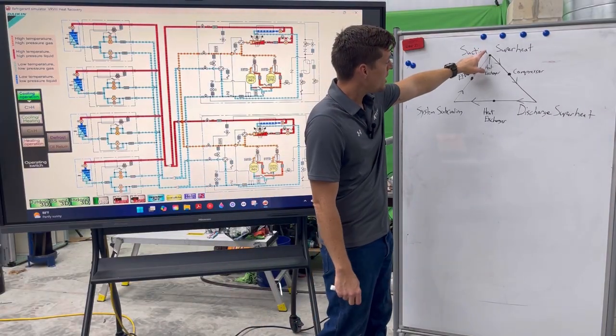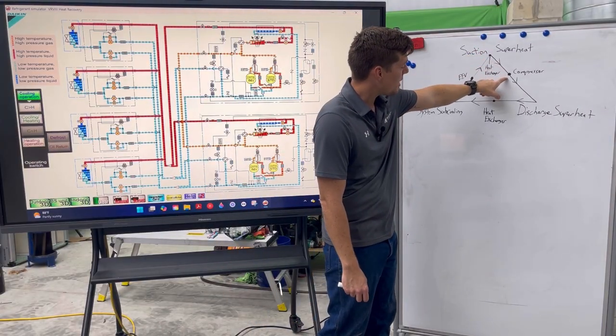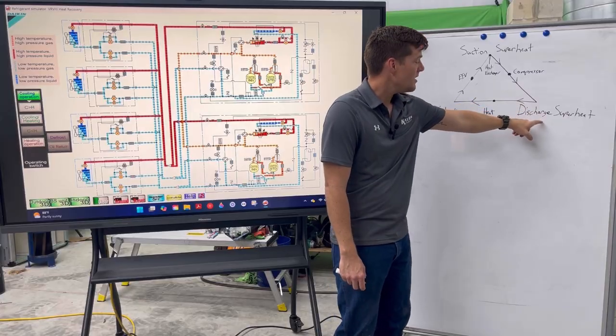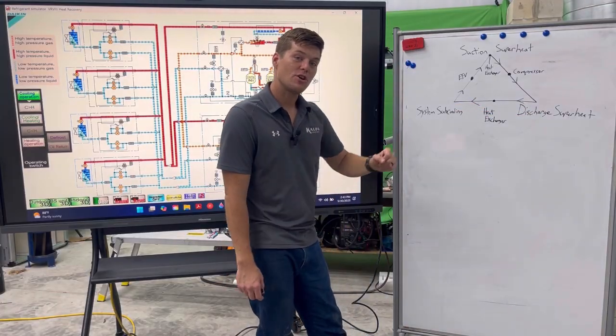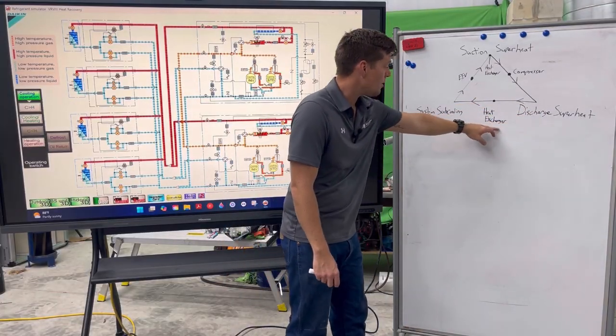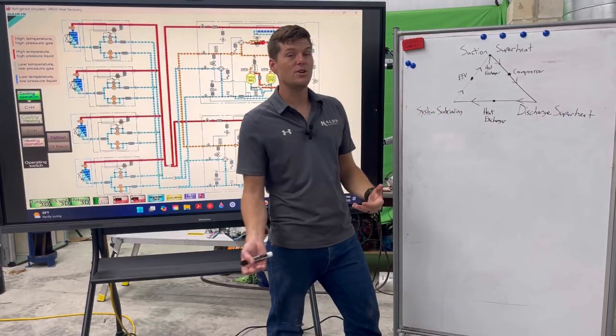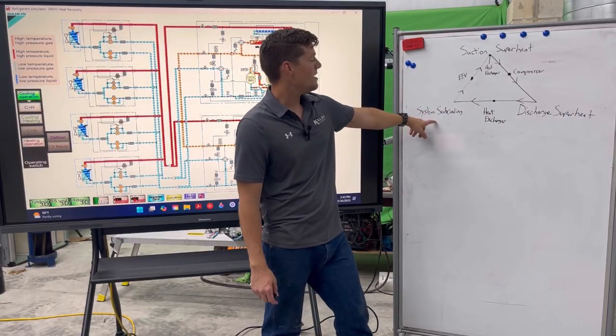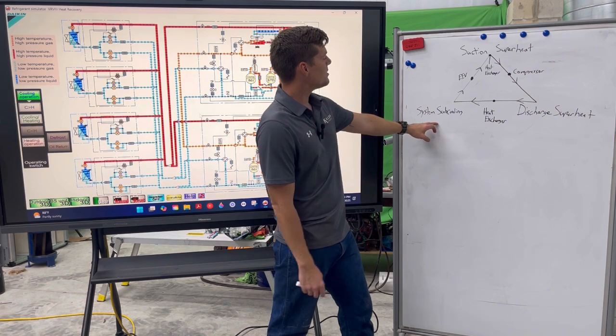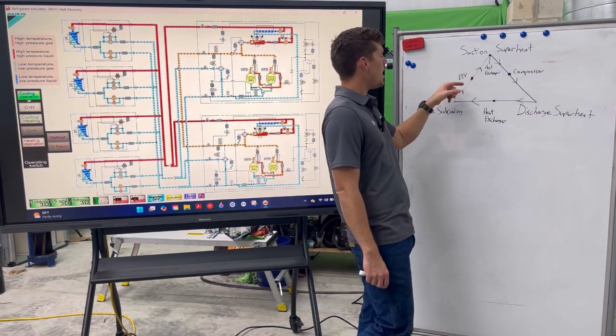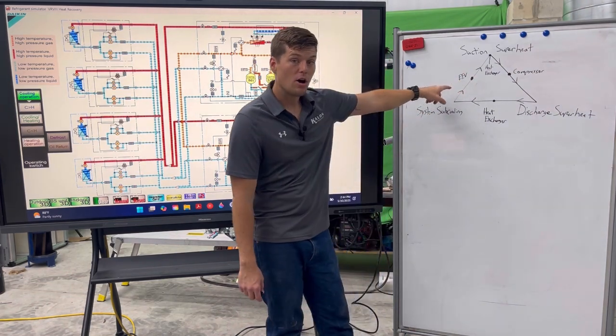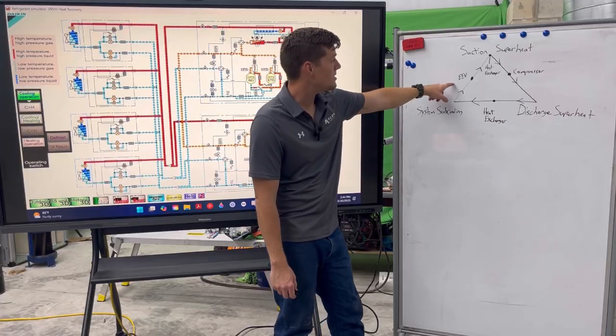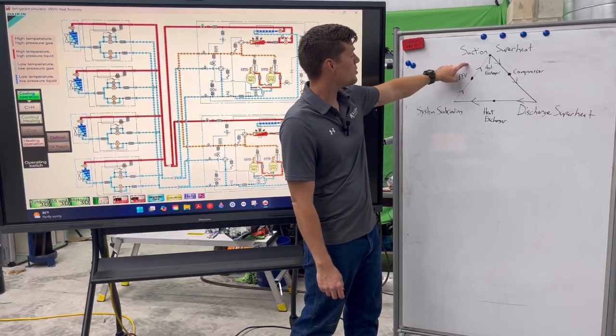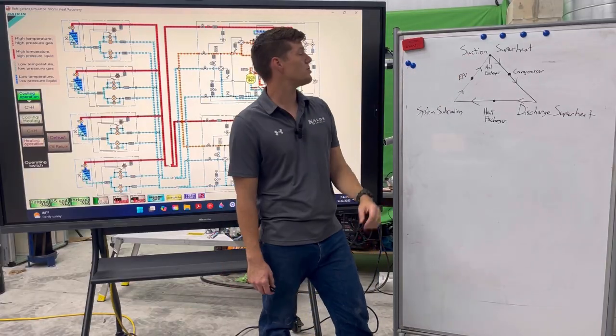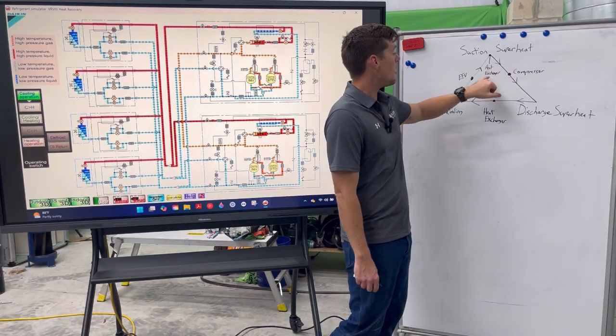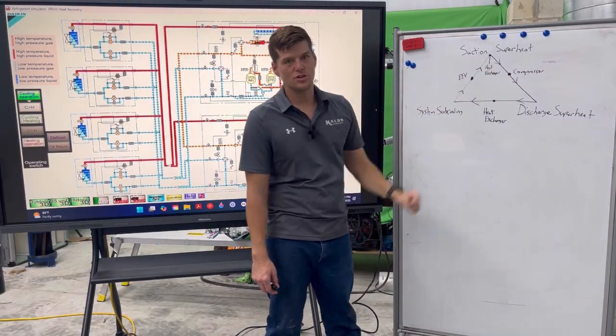From suction superheat, we go down through our compressor, out the other side, and we get discharge superheat. From discharge superheat, we then move across here through our heat exchanger, whether it's indoor or outdoor, and out the other side, I get system subcooling. Then from system subcooling, we're going to jog back up to the top of the triangle. We're going to go through our electronic expansion valve, our metering device, and on the other side, go from a liquid down to a saturated liquid in a low pressure state. And from here across our heat exchanger again, we get suction superheat.